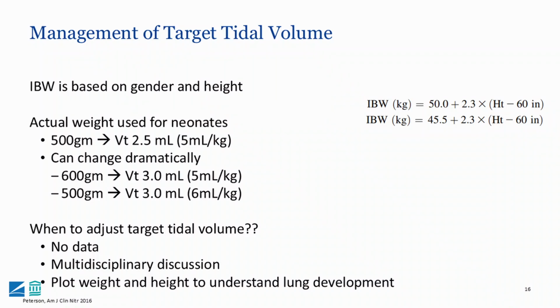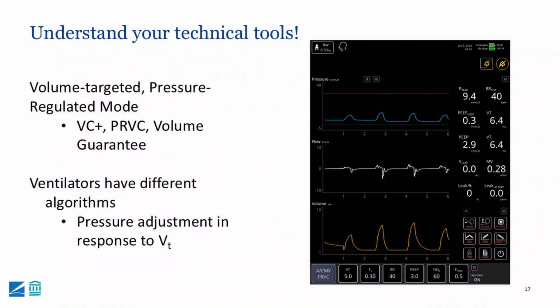Something that's common in our NICU is accepting a transfer in of a sick neonate, and we have to make sure that we're understanding and talking the same language when we're discussing ventilator settings to make sure that the baby continues to be supported as they're transferred over. So the generic terminology is volume targeted pressure regulated mode of ventilation. Some ventilators call it VC+. This ventilator here calls it PRVC. Other ventilators in more of a spontaneous mode call it volume guarantee.